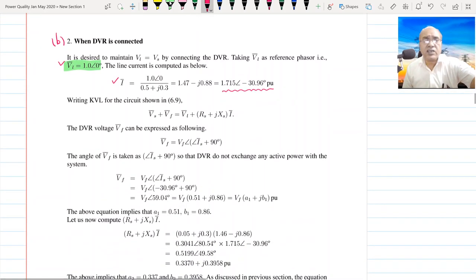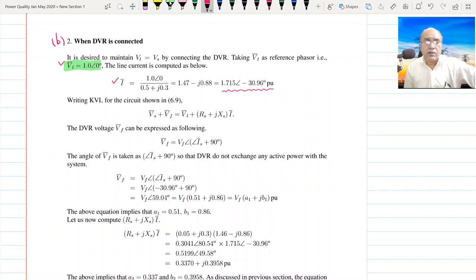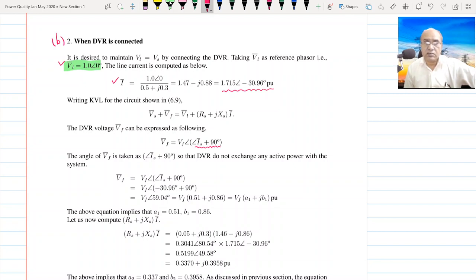With this current we can find out the value of VS + VF, which will result in a quadratic equation in VF as we have solved earlier. The angle of VF is equal to the angle of IS plus 90°. This ensures there is no active power consumed in the operation of the DVR.